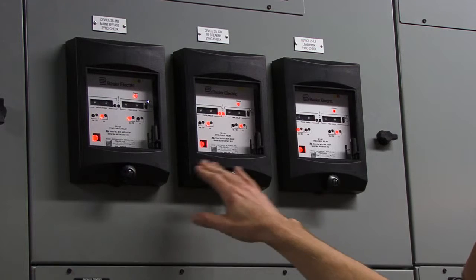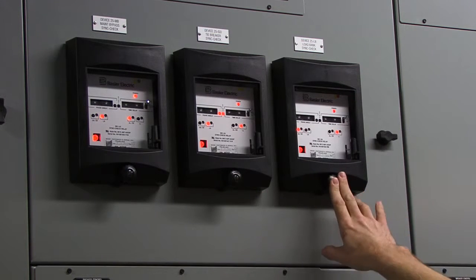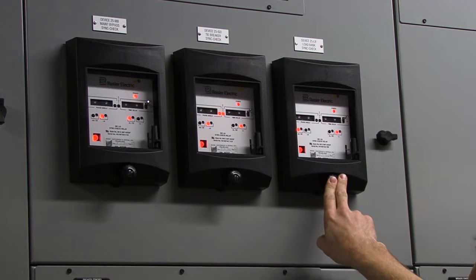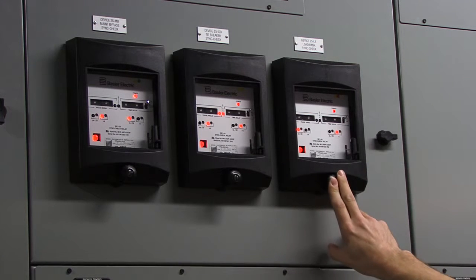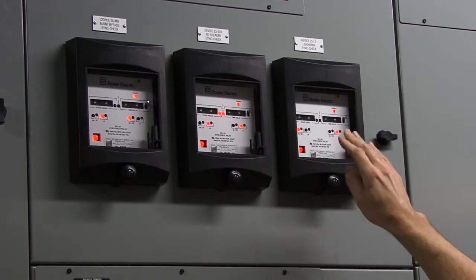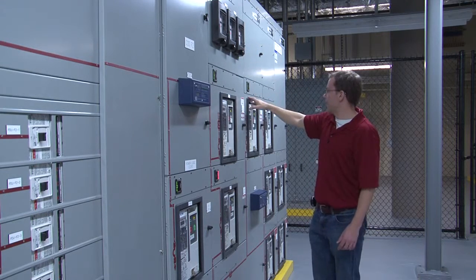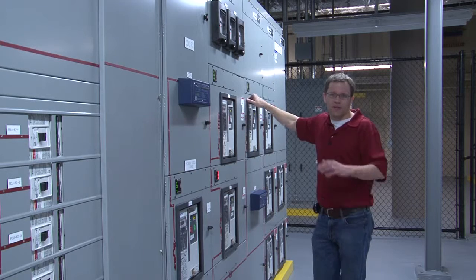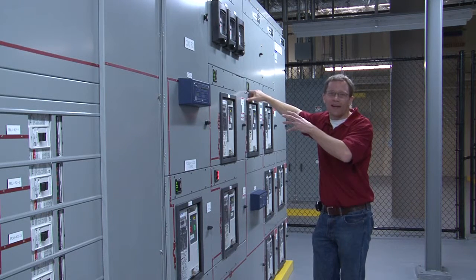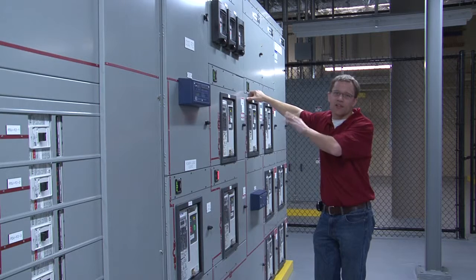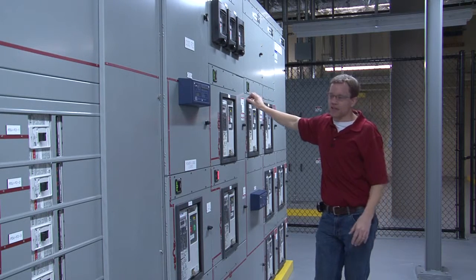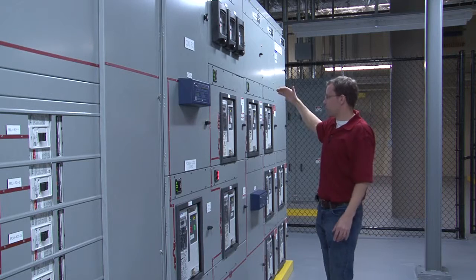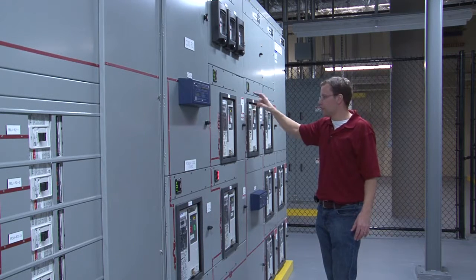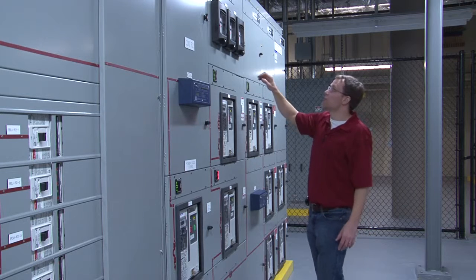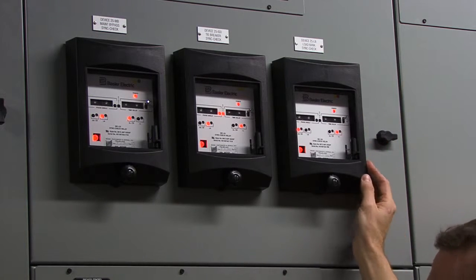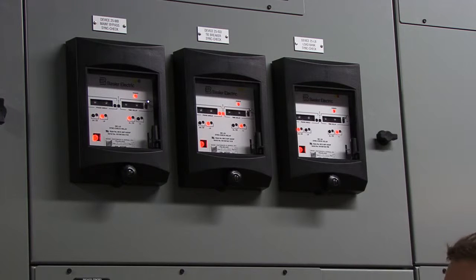These relays are not set the same. The load bank sync check relay has a 0-degree sync window because you are never to close the maintenance bypass, the load bank breaker, if the bus duct that it feeds is already energized. You would always want to be energizing a de-energized bus duct. So the bus side of this breaker, which is the bus duct itself, should be dead whenever this breaker is closed. So the sync check relay won't allow you to close it if both sides of the breaker are hot, even if they're in sync.